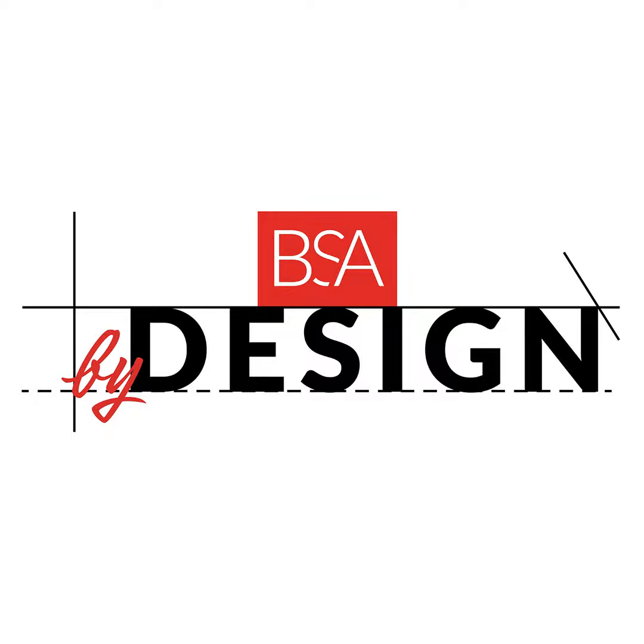Sometimes all the equipment moves. So that's the other thing. What are you allowing for? If it moves on the floor, that's a different animal because you've got to provide space for it structurally. But going back to allowing the flexibility of the equipment is probably the biggest thing that you can do from a design standpoint. When it's happening later in the process, what are some of those common issues? And I'm assuming, obviously, you've talked about it, budget, timeline, there's spatial considerations as well? Yeah, there's spatial considerations. There's structural and utility changes.